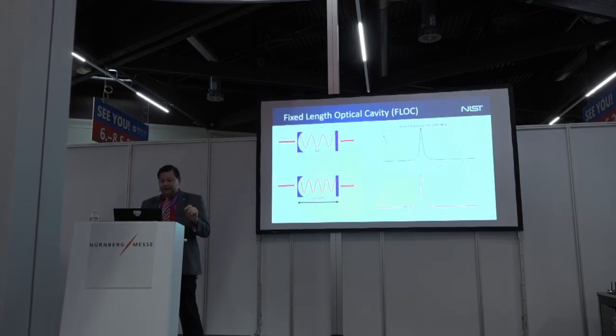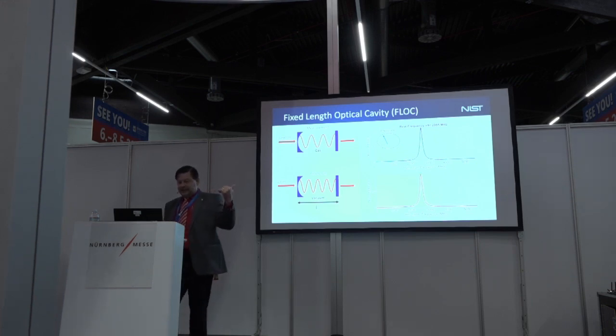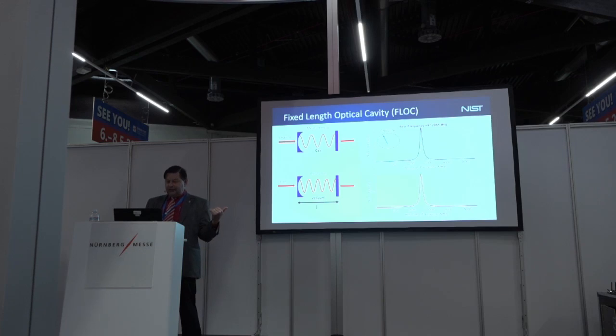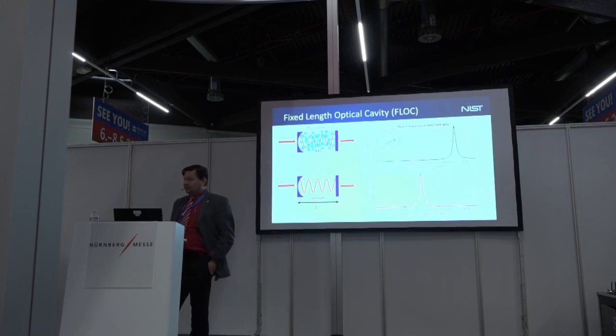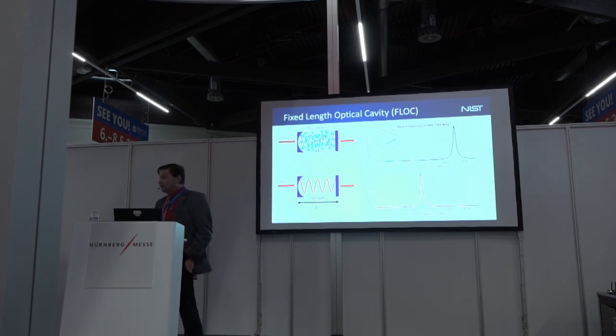Okay, so here's a little video animation of what I just showed you. So think of the top cavity as having the gas, and the bottom cavity is now at a vacuum. And on the graph over there, you see a pressure gauge. And now I'm going to start the animation. You're going to see the pressure go up. And there it goes. And what happens is we now have to change the frequency going into that cavity. What we're going to do to make our math much easier is we're going to do something called the beat frequency. And all you do is you subtract the frequency of the stable vacuum cavity from the measurement cavity. And now instead of trying to make measurements in the megahertz range, you're making measurements in the kilohertz range.